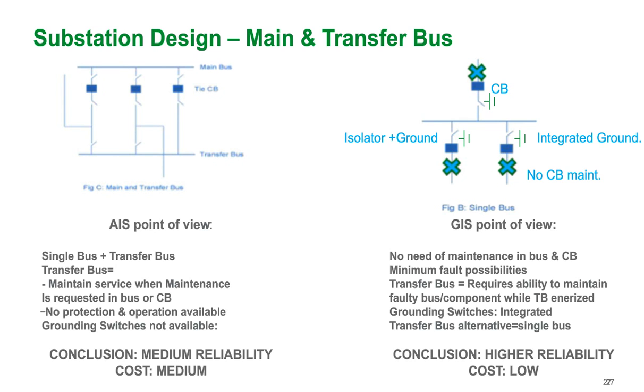Now from the GIS point of view, typically a transfer bus is not needed. So typically as an alternate to transfer bus, we would propose a more simple and cost-effective single bus arrangement. This is because you don't need to have that routine maintenance on the circuit breaker, and you don't need to have that routine maintenance or inspection of the bus bar. So you get, again, the higher reliability of the GIS, and you keep your costs much lower because it's a lower complexity of design.